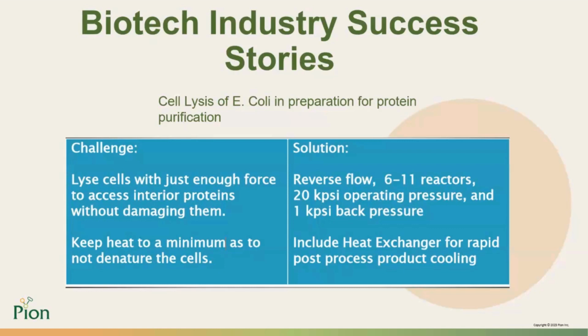The solution Pion's technology offered was found optimized with a reverse flow setup, either 6 or 11 reactors, 20,000 psi of operating pressure, and 1,000 psi of back pressure. This setup did include a heat exchanger for rapid post-process product cooling to control the temperature that the product was exposed to. This setup was found to effectively lyse the cells and to maximize yield.